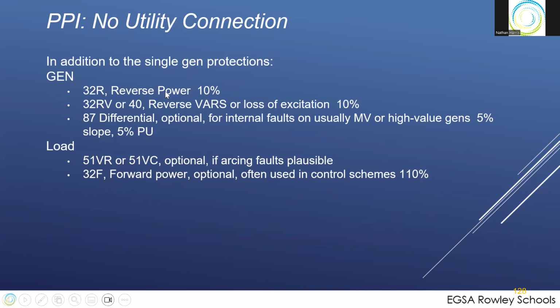If you have a PPI, do the same settings plus reverse power 10%, reverse vars at 10%, differential if you've got it at 5% with the 5% pickup and slope. Load, if you've got arcing faults possible, you'll want to use a voltage restrained or voltage controlled relay, perhaps. In that case, you could set them for 70% voltage and 100% current. So if the voltage drops to 70, they'll trip immediately. 32F forward power, often used in control schemes more than protection schemes, but 110% is reasonable. Put out more than 110%, you should trip off within a second or two.